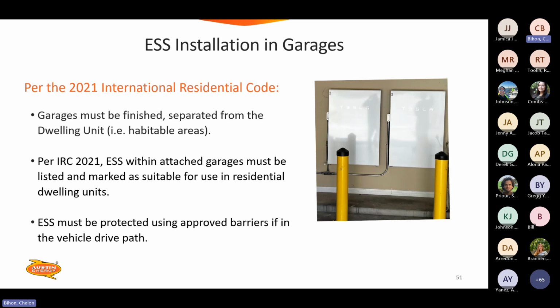Per the 2021 International Residential Code, garages must be finished, separated from the dwelling unit. That's an International Residential Code requirement of sheetrock and the doors between the dwelling unit to keep them separated is what that is referring to. And that's more of a fire hazard separation. Per IRC 2021, ESS within attached garages must be listed and marked as suitable for use in residential units. That's an attached garage for sure, and listed and marked for suitable use. ESS must be protected using approved barriers if in the vehicle drive path.